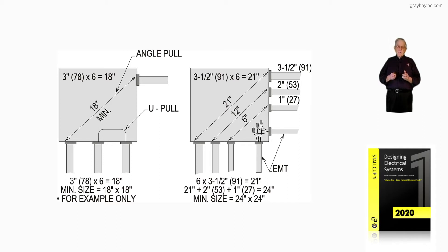Based upon a 3-inch conduit, that distance would allow you to pull the largest conductors permitted in that raceway and make a 90-degree turn and make that angle pull. The U-pull down at the bottom, you're doing the same thing. You're having the separation so that you can come in and make two 90-degree bends on your conductors into the conduit.